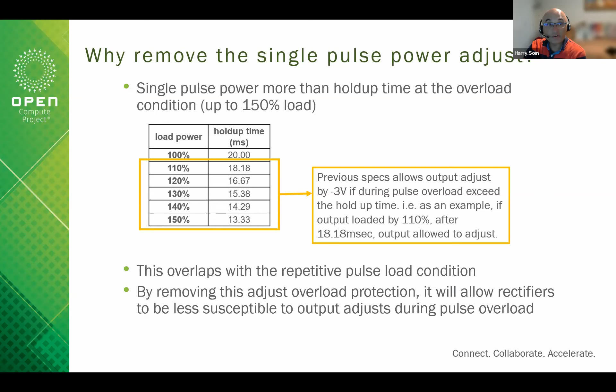For this load condition, you see when the load goes from 110% to 115%, the actual time to adjust is 103 milliseconds, all the way down to the worst case, the 150% DC to DC peak load, where the time to adjust is still 21.59, more than the actual hold-up time. The spec time in this condition is 16.28, so we have margin there, and under all conditions we have adequate margin for this operation. The orange line shows the comparison versus spec, so we're performing well under all those conditions.